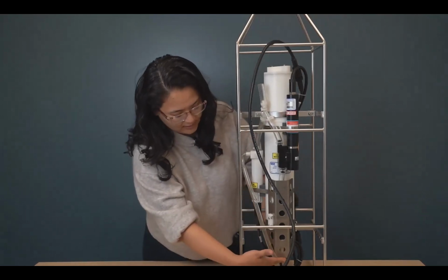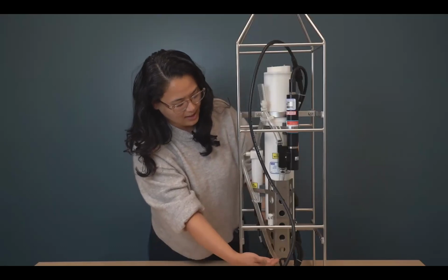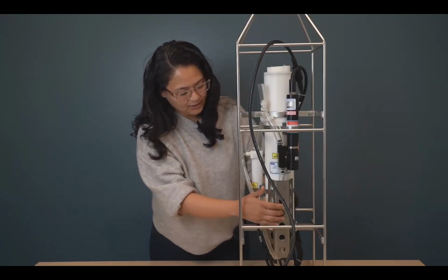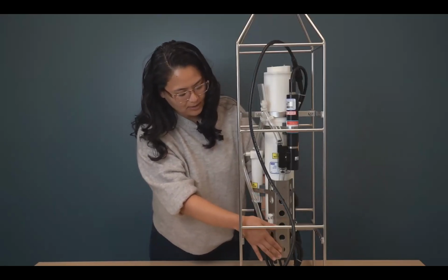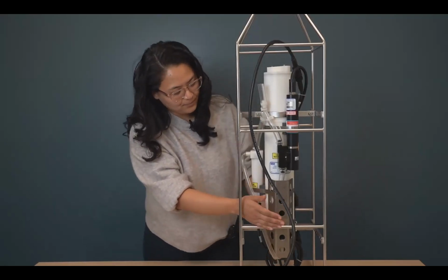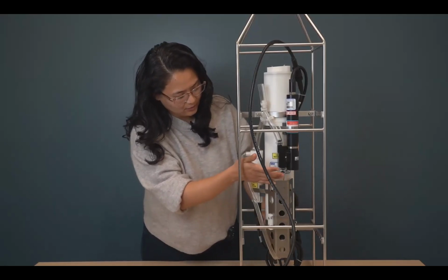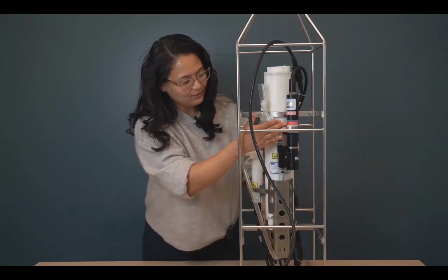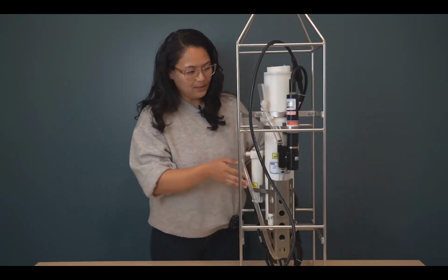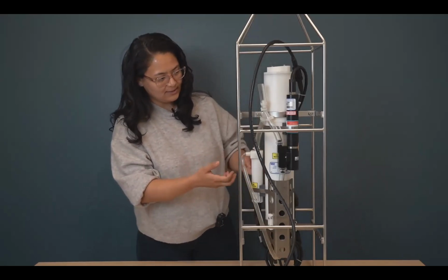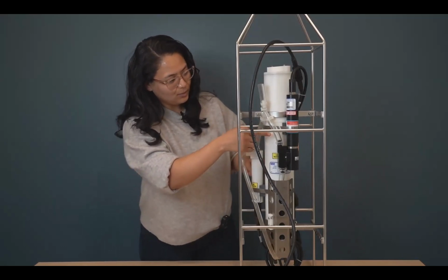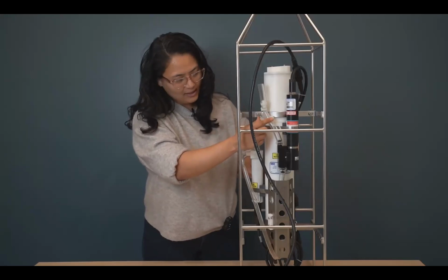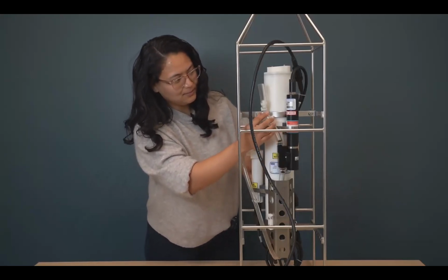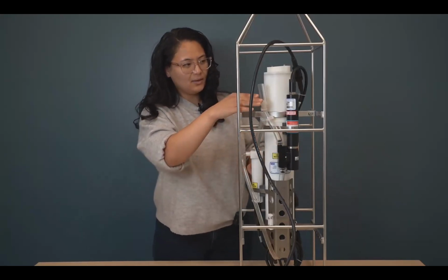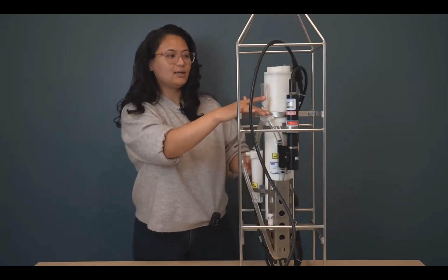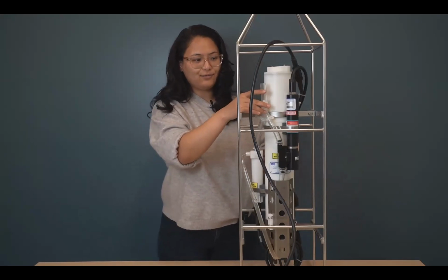The water goes in through here, which is the water intake. This is the guard cell, and underneath the guard cell, you have the temperature probe and the conductivity probe. The conductivity cell is then connected through all the Tygon tubing to the SBE 43 dissolved oxygen sensor. The pump over here pulls all the water in to the system, and the Y fitting connects the whole system in this area, and we have the air bleed, which is super important for the bubbles to be released from the SBE 19+.